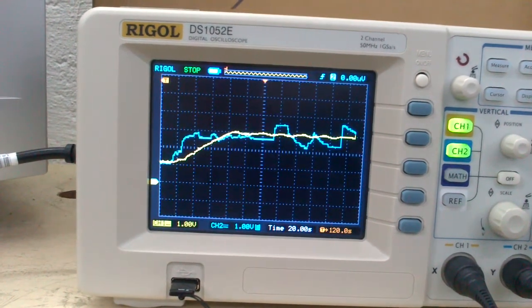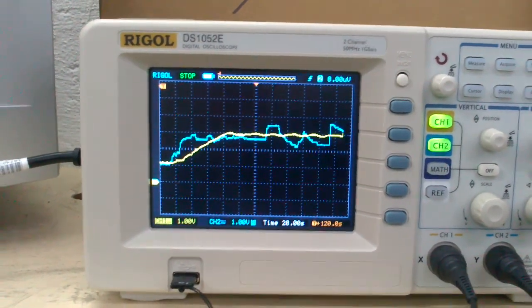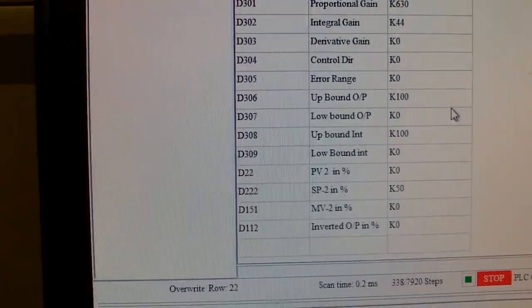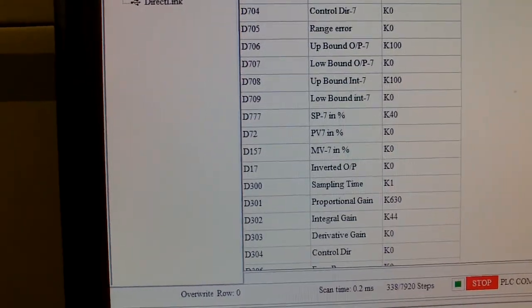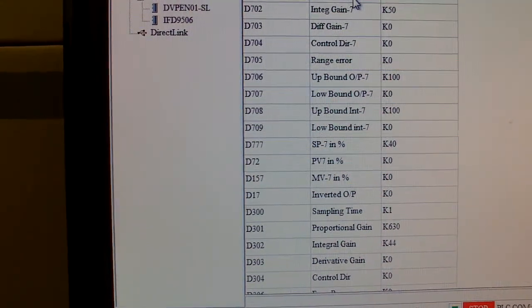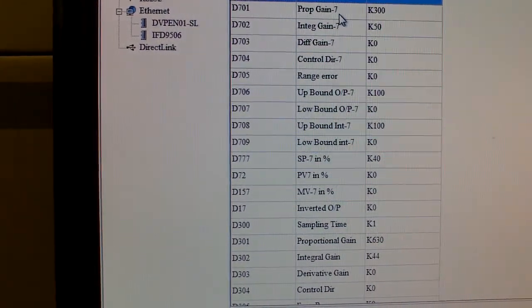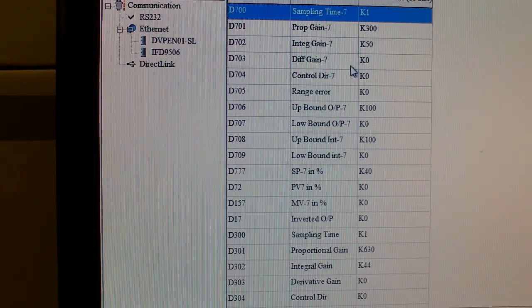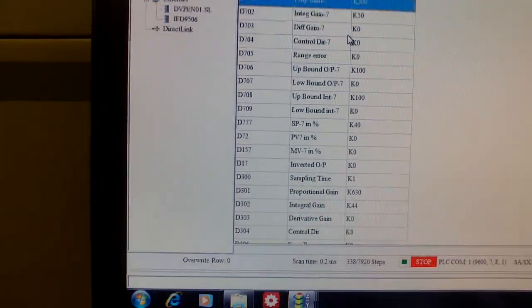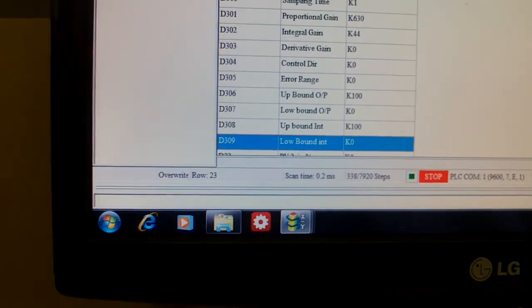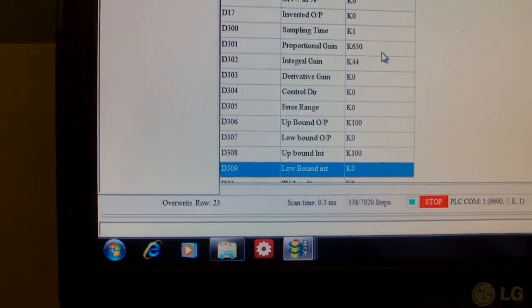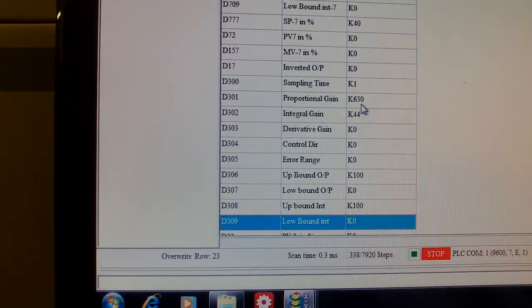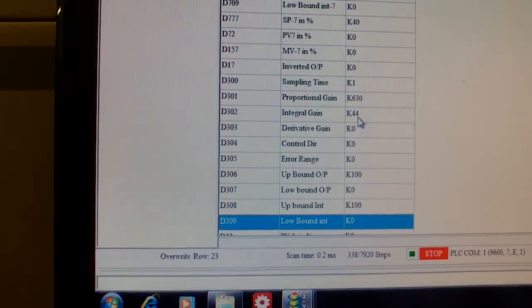The previous values that I used are these ones. Let me show you the set point. The proportional gain on tank 7, the one up there, is 3 and the integral gain is 0.5. My derivative is set to zero. Now on tank 2, the proportional gain was 6.3 and the integral one is 0.44.